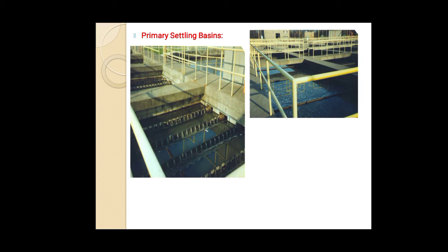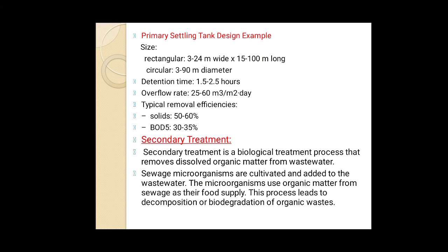Then the detention time for this settling tank is 1.5 to 2.5 hours. Then the overflow rate is 25 to 60 cubic meters per day. And typical removal is 50 to 60% of solids, and 30 to 35% of BOD. These are done in this primary settling tank. Here the primary treatment is over.